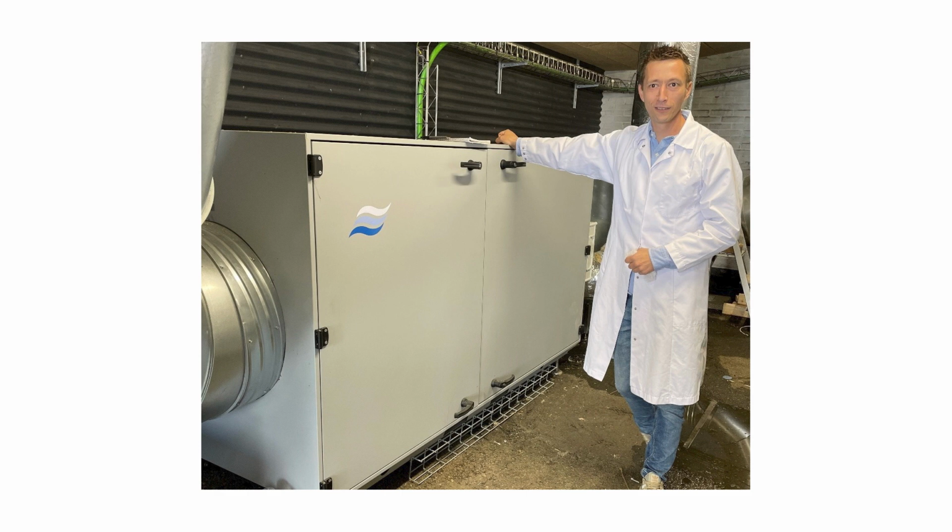Well, the outside moisture quantity is calculated using the known humidity and temperature of outdoor air, and the rate of air exchange within the area in question, the physical size of the area, and lastly what humidity and temperature it ultimately needs to be. And once all these details are determined, a psychrometric calculation can be done. Now, this precisely determines the volume of moisture the dehumidifier will need to remove from the incoming outside air to meet the required indoor condition. Now, this calculation is something that a dehumidifier manufacturer will be able to provide guidance on. And how about the water coming from inside?